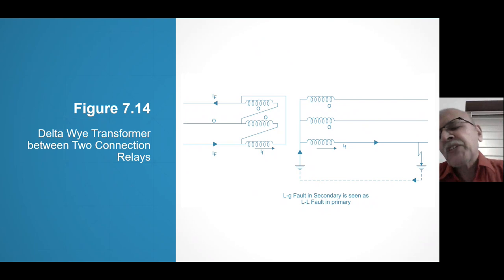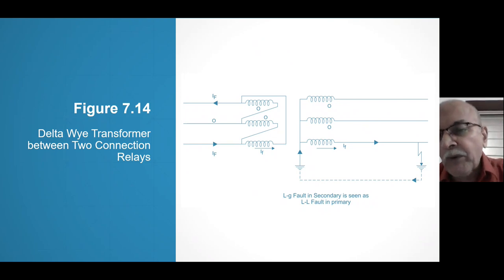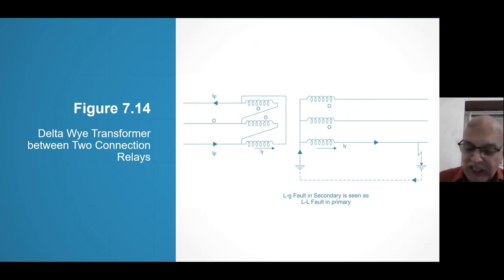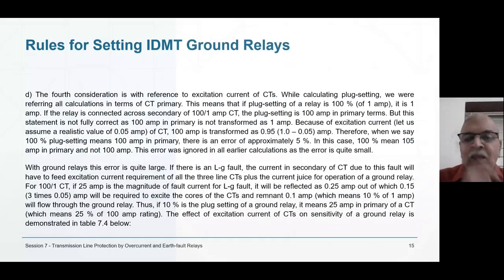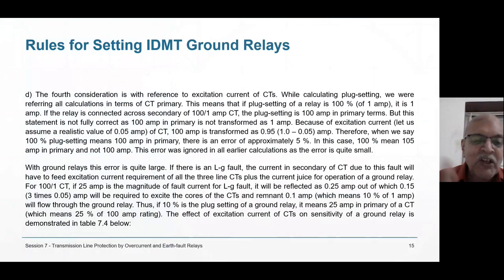In the residual connection, three CTs are involved, so three times the magnetizing current is required. The total excitation current drawn is 3 × 0.05 = 0.15 A. So if relay plug setting is 5% (0.05 A) and excitation current is 0.15 A, the actual primary current needed to operate the relay is much higher than expected, meaning the stated sensitivity of 5% does not correspond to actual sensitivity.